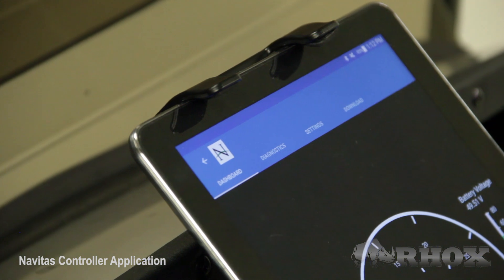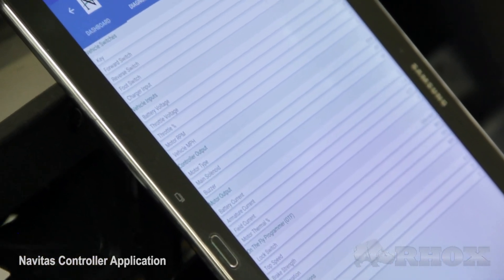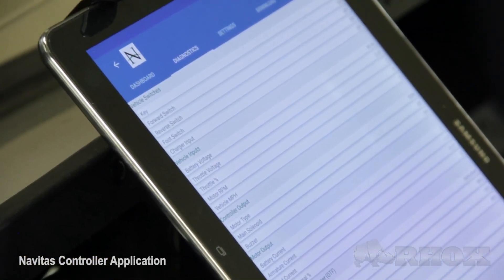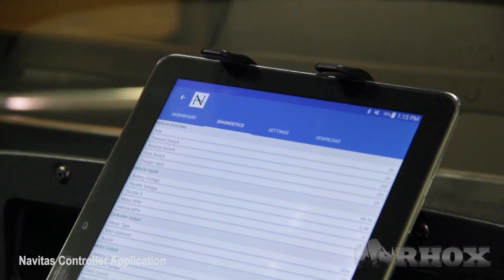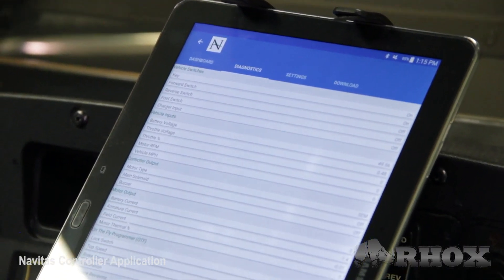Next we're going to move on to the Diagnostics tab. On this tab you're going to be able to see some key performance features on the controller and the settings currently in the controller — things like the current key switch position, throttle percentage, motor RPM — things that you're going to need to tweak the performance of the controller.